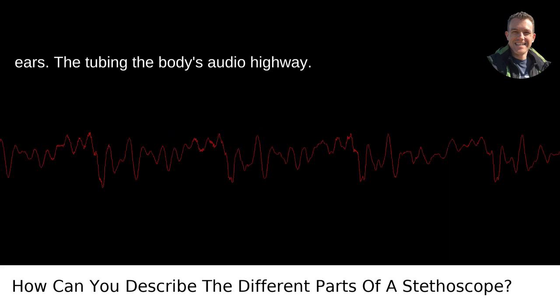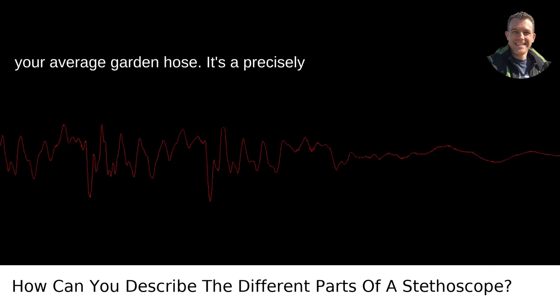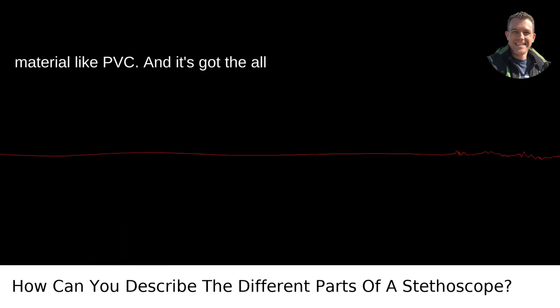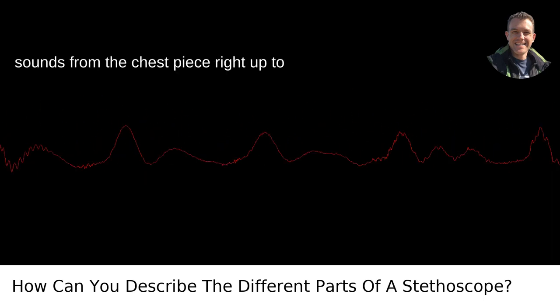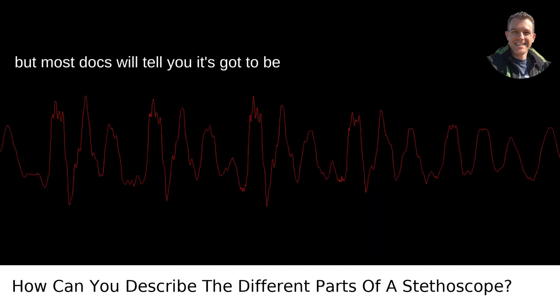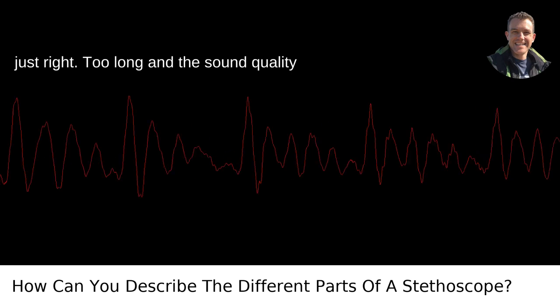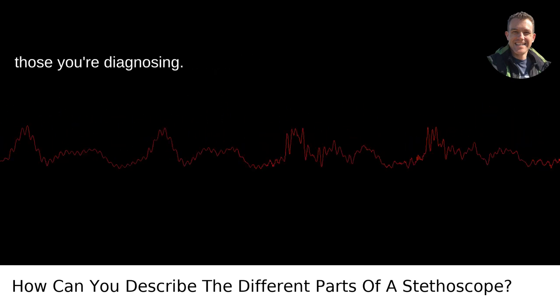The tubing, the body's audio highway. Next up, we've got the tubing. This isn't your average garden hose. It's a precisely designed tube, often made of a flexible material like PVC, and it's got the all-important job of carrying the body's sounds from the chest piece right up to those eartips. The tubing length varies, but most docs will tell you it's got to be just right. Too long and the sound quality drops. Too short and you're getting a little too up close and personal with those you're diagnosing.